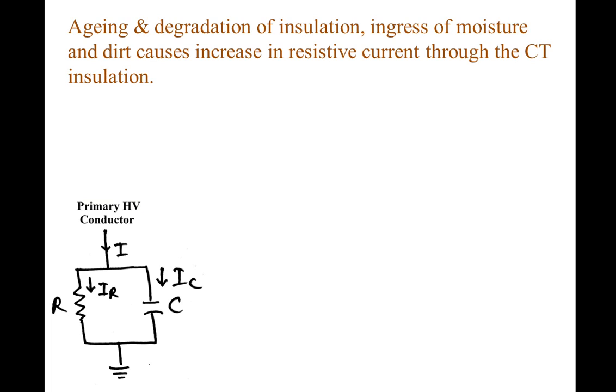Various factors such as aging, degradation of insulation, and ingress of moisture and dirt cause an increase in resistive current through the CT insulation. Therefore, in addition to the capacitive current, a small resistive current also starts flowing through the insulation.